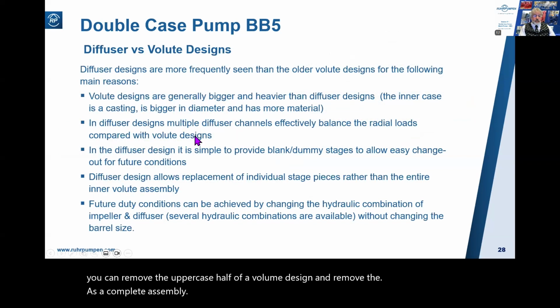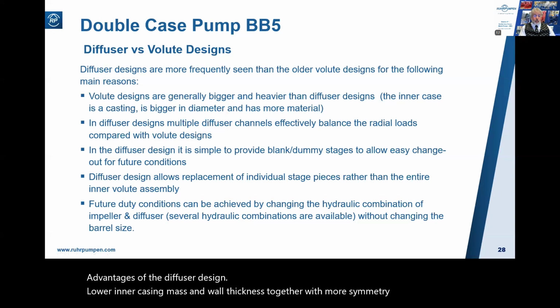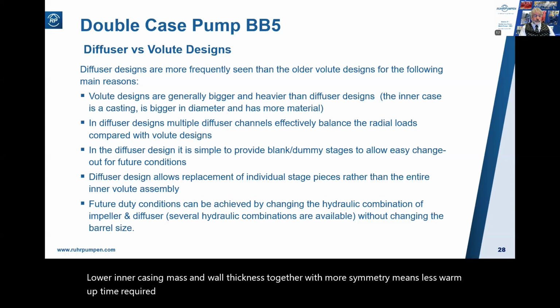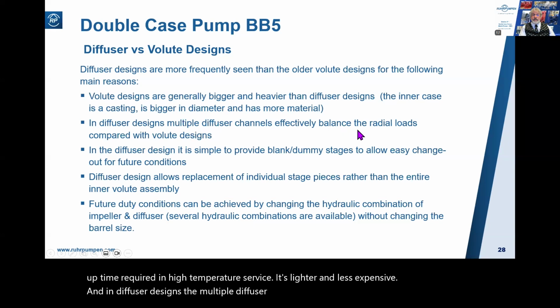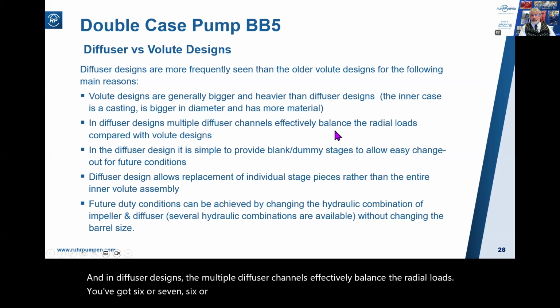Advantages of the diffuser design: lower inner casing mass and wall thickness, together with more symmetry, means less warm-up time required in high temperature service. It's lighter and less expensive. And in diffuser designs, the multiple diffuser channels effectively balance the radial loads. You've got six or seven diffusers, as opposed to two volutes in the double volute design. So intrinsically, the balance is tighter.